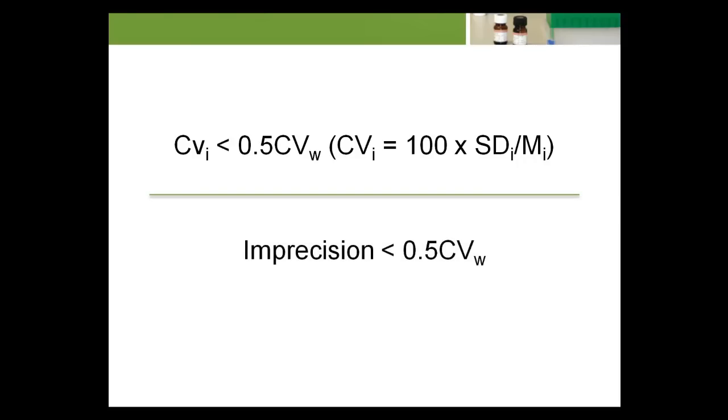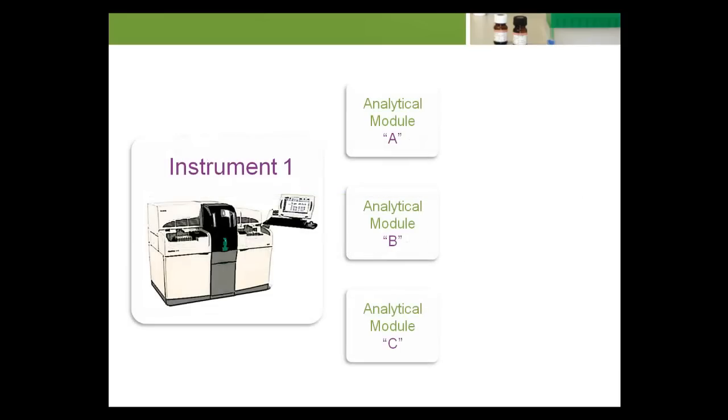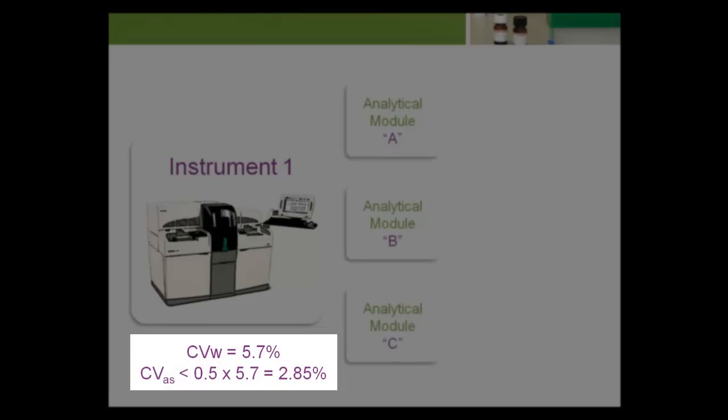On the other hand, if modules have different means, bias exists between modules. The imprecision of the individual modules must be substantially less than 0.5 CVW for the total analytical system to meet the goal. For example, assume a lab has three analytical modules that test glucose. The within-individual biological variation for glucose reported by Ricos is CVW equals 5.7%. Therefore, the lab's goal is CVAS less than 0.5 times 5.7 equals 2.85%.